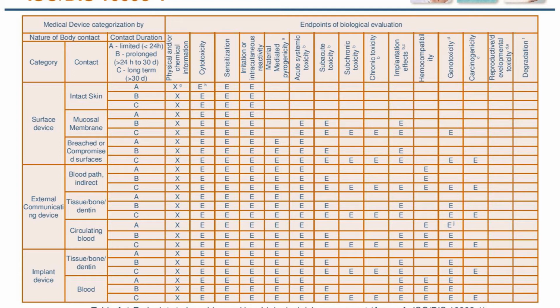If we zoom the table in some parts, we can see that, for example, the first column that is now included in the table is related to the physical and chemical information. So, physical and chemical information about the medical devices are now the first step of the biological evaluation. And in particular, they are requested for all kinds of medical devices, as you can see in the table. Basically, even if you have a skin contacting device, an implant device with permanent contact, you need to provide this information. And moreover, this information is considered a prerequisite for the risk assessment. That means that you should collect this information before performing any kind of biological testing. So it's really now important. And how can we address this endpoint?